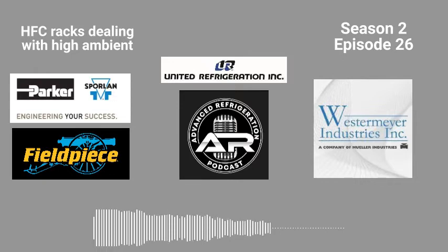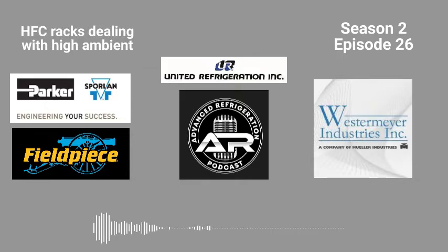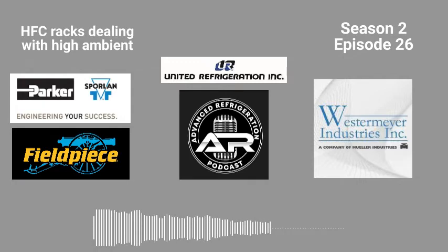If you're going to spend that much money doing a remodel and doing all the other stuff, if your condenser is 15, 20 years old, it might be time to change it, especially if you're changing a bunch of the load that's on there. Obviously, you want to make sure the condensers are clear, that there's no carpets, because a lot of times construction will mess with you. If you have more construction in one area, throwing out a lot of dust, it gets sucked up in there.